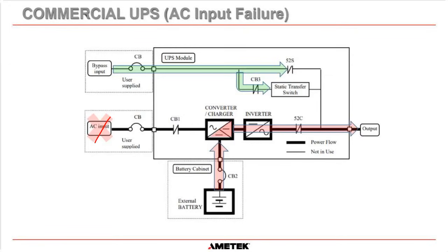And then if we have a power failure, then we go on to battery. And you can see the battery is now coming up here. Once again, it's a 480 volt nominal system, but it does go through this electronic DC to DC converter, and it converts the 480 volts up to around 650 volts. So there is conversion happening there. There is electronic circuitry required to get that 480 volts to 650 volts. But then the other operation is as if nothing has happened. The inverter still carries on regardless, and the contactor here is closed.